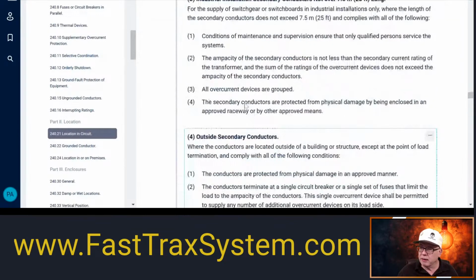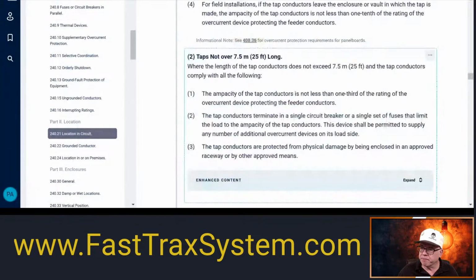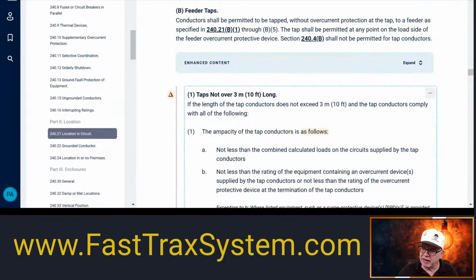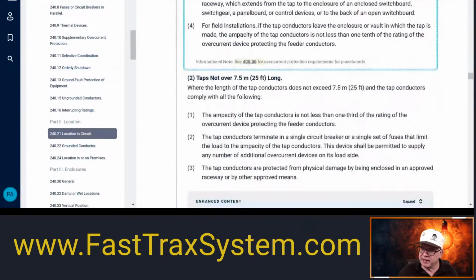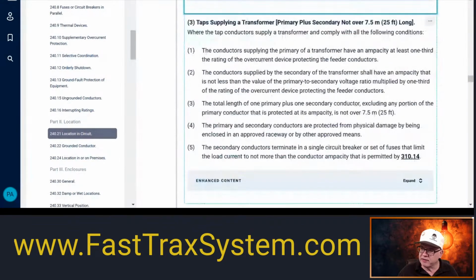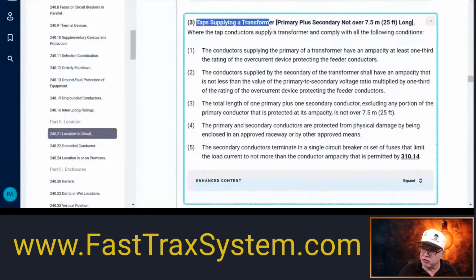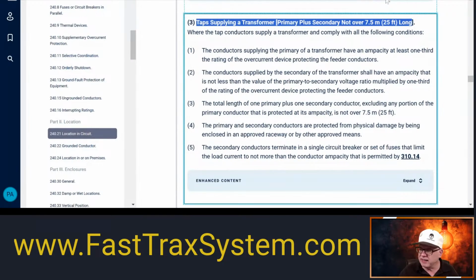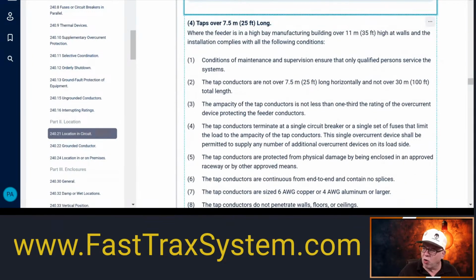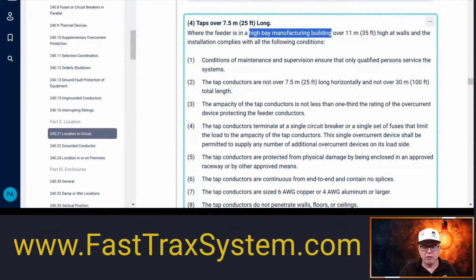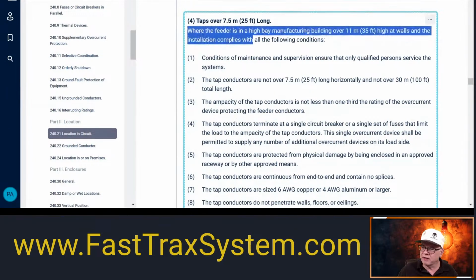And we have secondary conductors not over 25 feet long. But when it comes to the feeders, we'll talk about all of these. We've got not over 10 foot, which we've covered. Not over 25 foot, which we covered. This is the one we talked about, the tap supplying a transformer where the primary plus secondary is not over 25 feet long, which we discussed in a previous episode. And then we've got taps that are over 25 foot long, and this happens to apply to high bay manufacturing buildings. So if you're dealing with an extremely high bay manufacturing building, with high lighting to accommodate larger trucks and larger things like that, then you have some allowances here that you can follow.